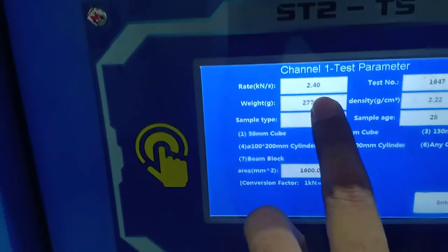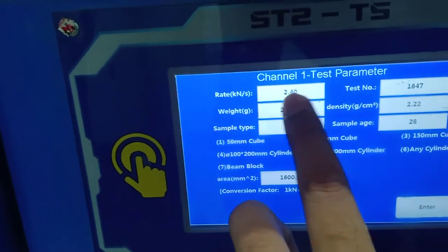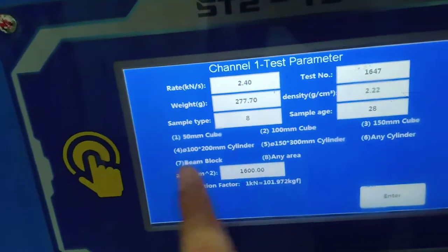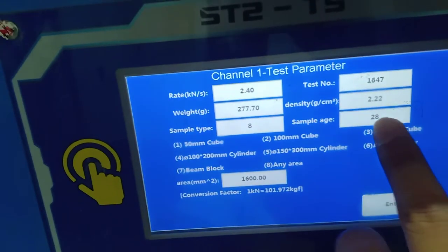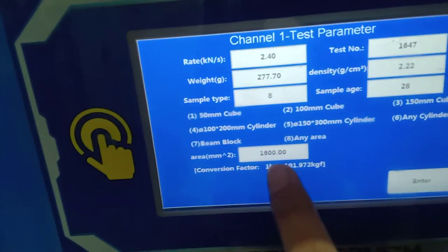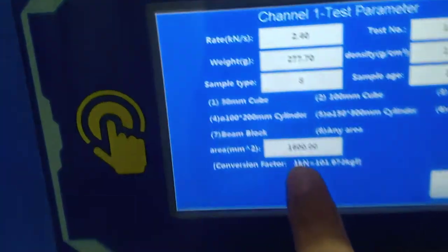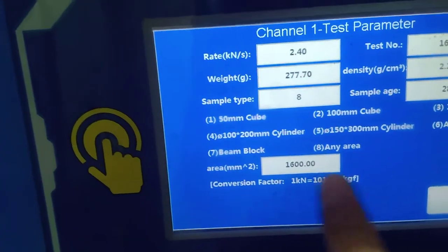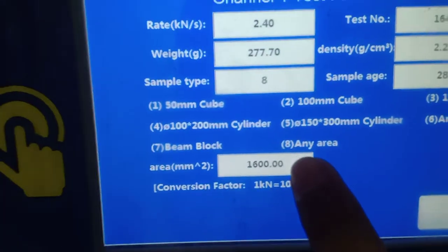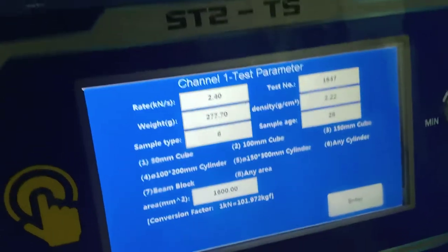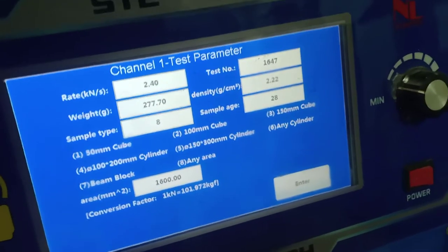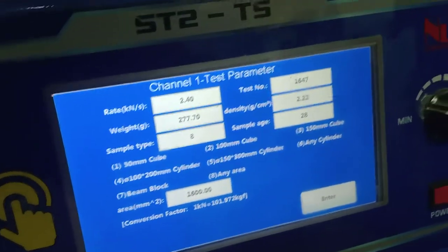I go to menu, then test parameters. I make the setting based on the standard: 2.4 kilonewton per second. I also enter the sample weight if density is needed, and the sample age and sample type. Different sizes are mentioned, but I am not using those sizes, so I click 'any area' and select 1600 — my sample is 1600 square millimeters, which is a 40 by 40 cross section.